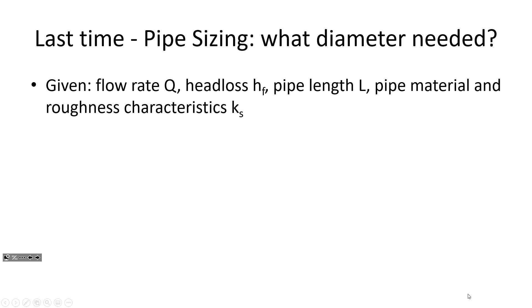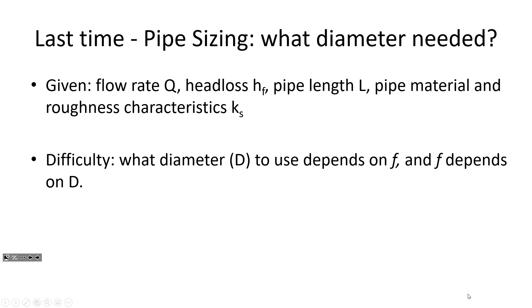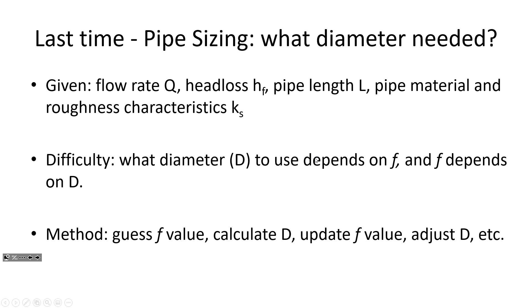Last time we went through a spreadsheet where for a known flow rate, a known head loss, and a pipe length, the pipe material was defined giving us epsilon or the relative roughness k_s. The problem with that iterative approach was that we were trying to find the pipe diameter, which depended on friction factor f, and f depended on the diameter. We solved this by guessing an f value, calculating the diameter, then updating f and adjusting the diameter iteratively until both the diameter and f value stabilized — that's when we knew we were done.